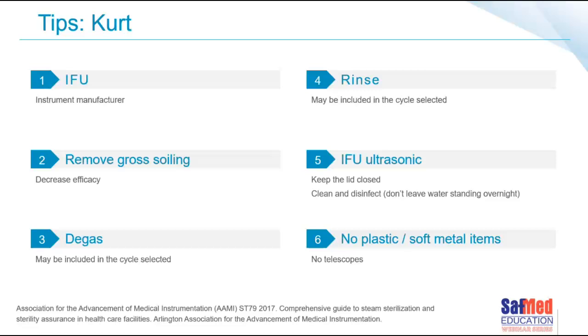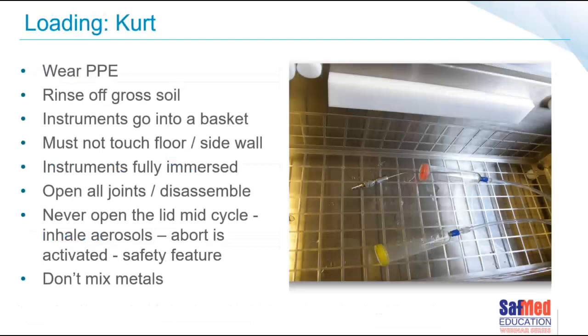If certain items, like the plastics that, like I said, cause damage during the cycle, or it just prevents the cycle from cleaning correctly. And please do not put any telescopes or electronic items in an ultrasonic cleaner. It will damage the instruments. Excellent. So even though we're doing laparoscopic instruments often in ultrasonic cleaners, we of course don't want to put in telescopes themselves, and we don't want to put in light guide cables or things like that. Again, like you said, following the manufacturer's instructions for use.